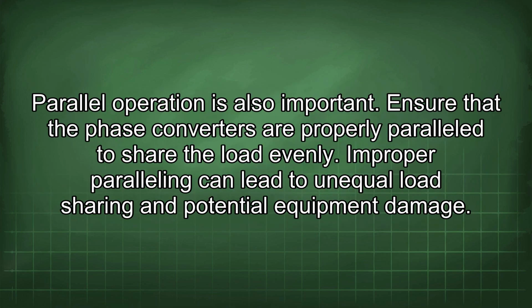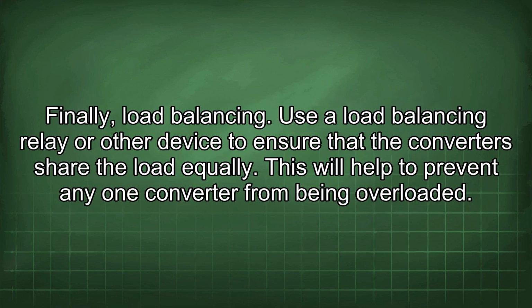Parallel operation is also important. Ensure that the phase converters are properly paralleled to share the load evenly. Improper paralleling can lead to unequal load sharing and potential equipment damage. Finally, load balancing. Use a load balancing relay or other device to ensure that the converters share the load equally. This will help to prevent any one converter from being overloaded.